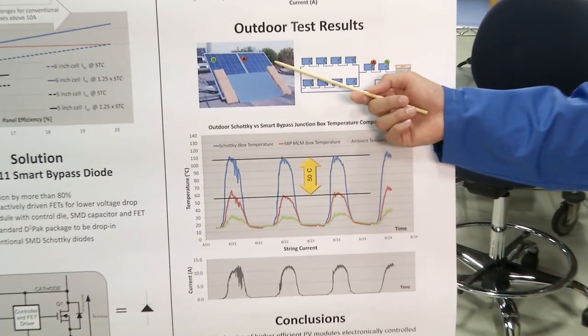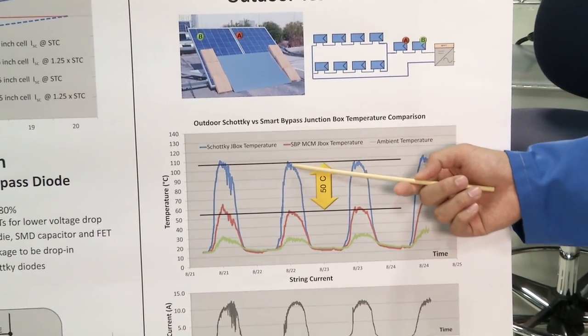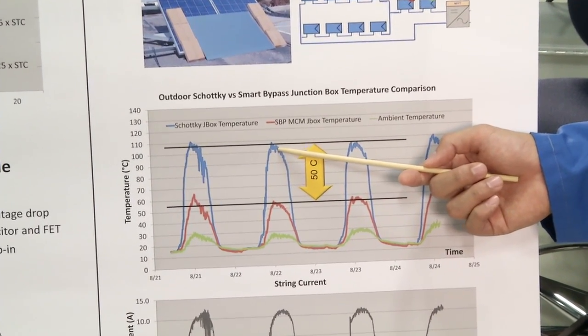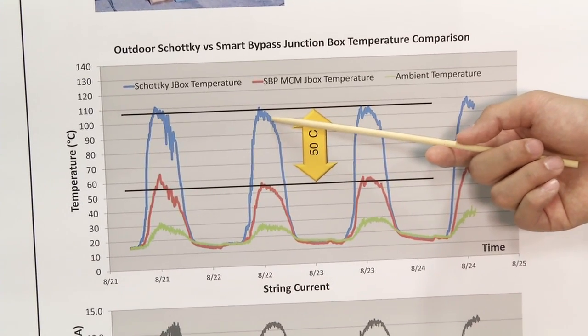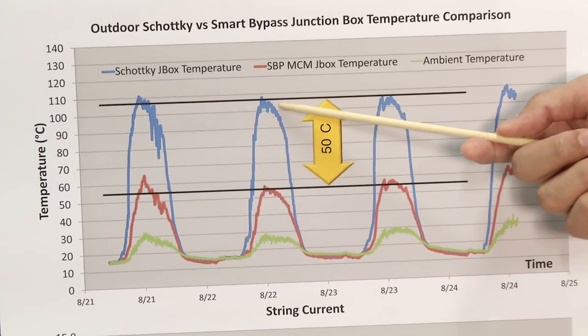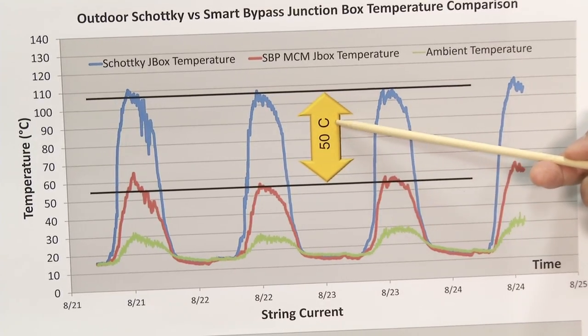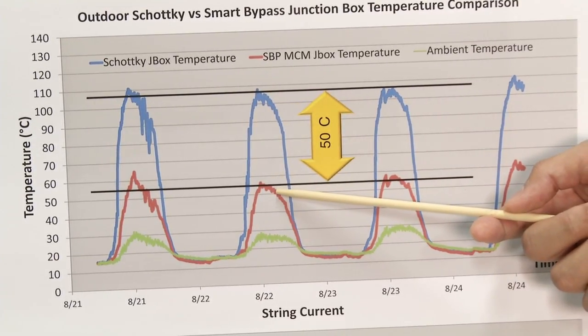We also took this junction box outside to be mounted on the panel for an outdoor test. Based on these test results, it is showcased that SM74611 exhibits less power dissipation compared to a regular diode. This will increase the reliability of PV modules. Also, our device has a lower leakage current compared to a Schottky. For more information, you can go to the website on your screen. Thank you for your attention and have a nice day.